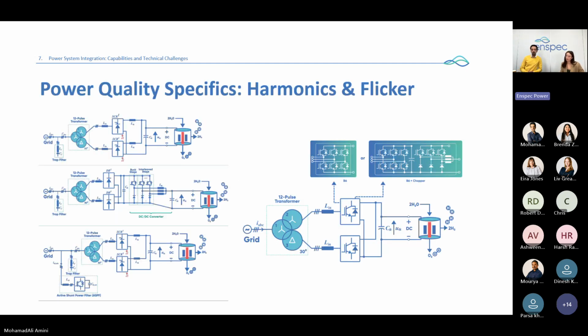If we look at the power converter station in more detail, it could have different configurations, from the simplest—6-pulse, 12-pulse—to the most advanced version of power converters, like active front-end conversion systems. Basic systems like 6-pulse and 12-pulse are more likely to need AC harmonic filters on the AC side, but this is less likely to be the case for active front-end converter configurations.